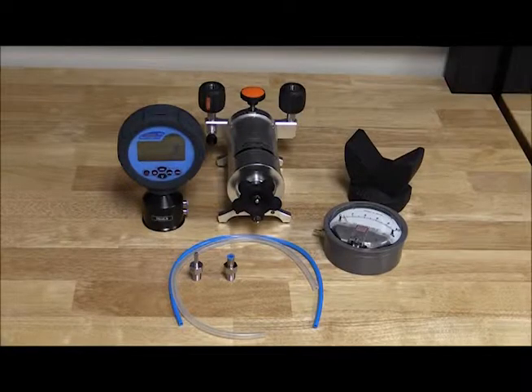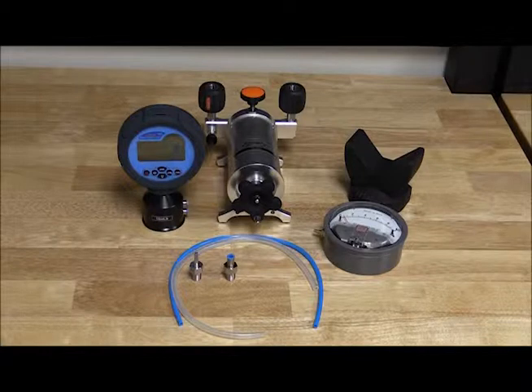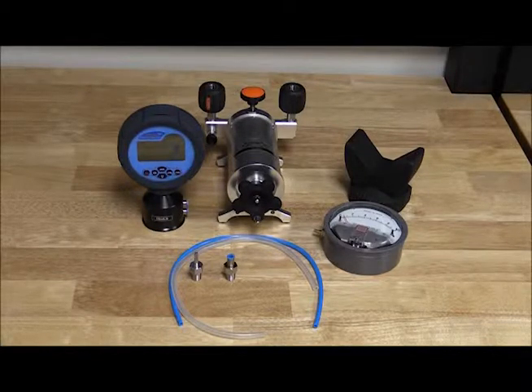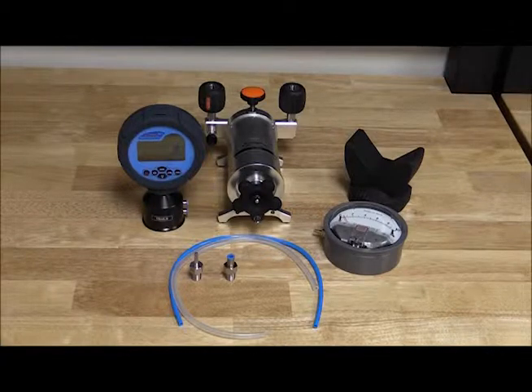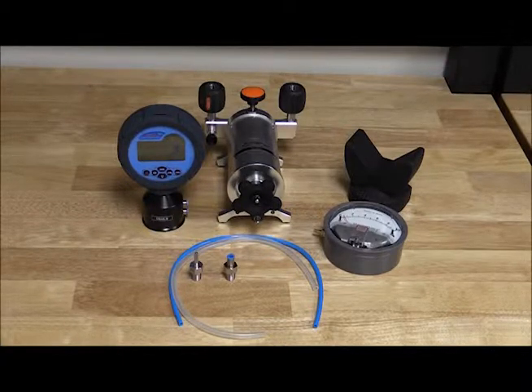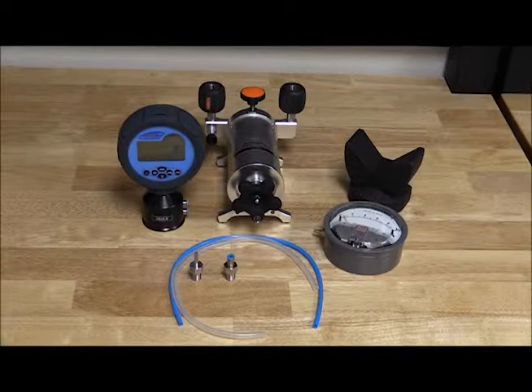In this example, we will use an Additel 901 pump to generate the pressure. The Additel 681 differential gauge will be used as our accurate reference, and we will be calibrating a magnehelic differential gauge that is 0-10 inches of water.